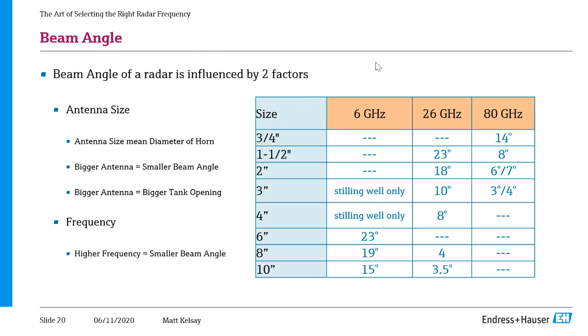So now if you look, instead of down the column, let's focus on, say, the 2-inch size antenna and move left to right. You see on the low frequency 6 gigahertz, we actually don't even offer a 2-inch antenna. It would just not really be well suited for really any type of application, so we don't offer it at all. On the 26 gigahertz, you have an 18-degree beam angle, and if you jump up to 80 gigahertz, you shrink that down to the 6 to 7 degree range. So quite a big difference keeping the same size of antenna, just moving up to the next frequency band.